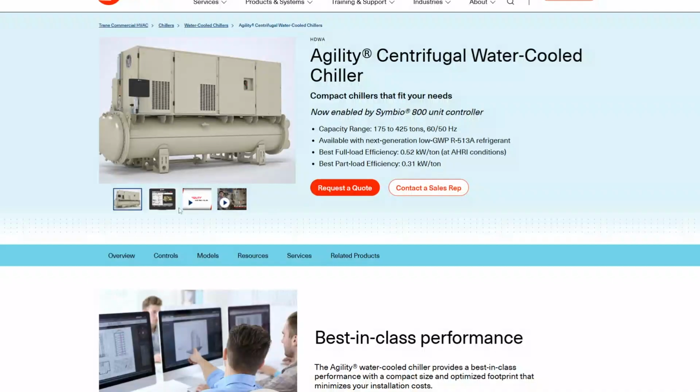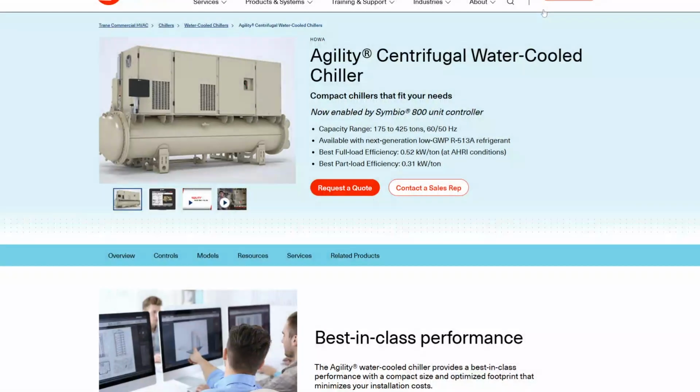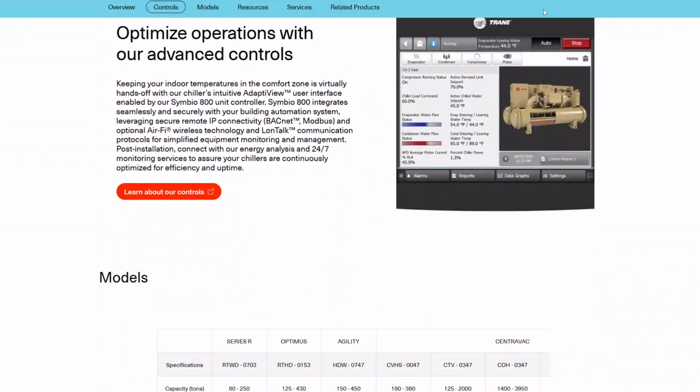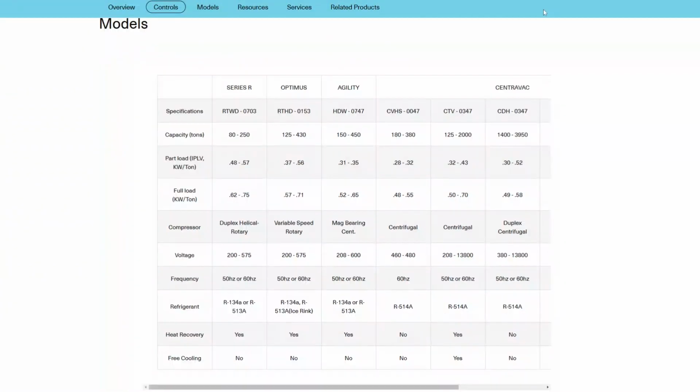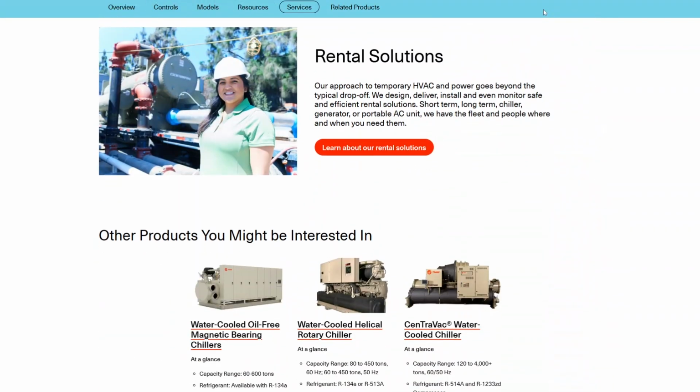The compression ratio for centrifugal compressors is somewhat limited, but they can support high refrigerant flow rates, so these compressors are widely used for large, steady loads. Centrifugal compressors are often employed for chilling water and air conditioning applications, but are rarely used in industrial refrigeration.